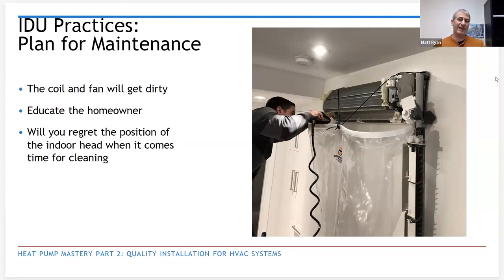Those, especially the fan blade, is on the supply side. So you get cold, moist air on that fan blade, it's going to start collecting dust, debris, and growth over time. So with commercial, we were finding we'd have to go in there every 3 to 6 months and do a deep clean. In a residential setting, if it's a cleaner home and they're keeping up on that filter once a month and getting that cleaned off, you might have to do that deep clean once a year, typically. Yeah, so those need to be gotten to more often than people know.